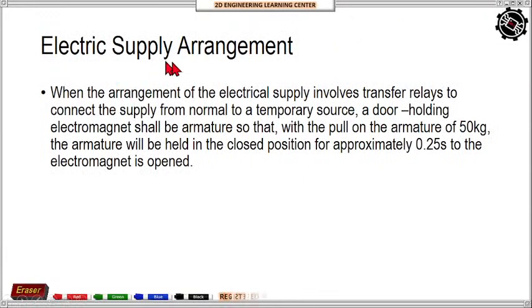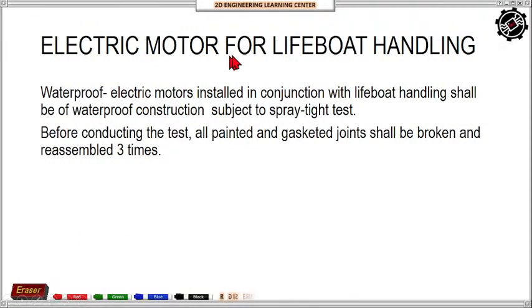Okay. Tapos, electrical supply arrangement. When an arrangement of the electrical supply involves transfer relays to connect the supply from normal to temporary source, a door holding the electromagnet shall be armature so that with the pull of the armature of 50 kilograms, the armature will be held in a closed position for approximately 0.25 seconds to the electromagnet is open. So this is to prevent unnecessary changing of the power from normal to temporary. So it should be able to hold, no, our the change over on 0.25 seconds. No, the pull of the armature is of 50 kilograms.